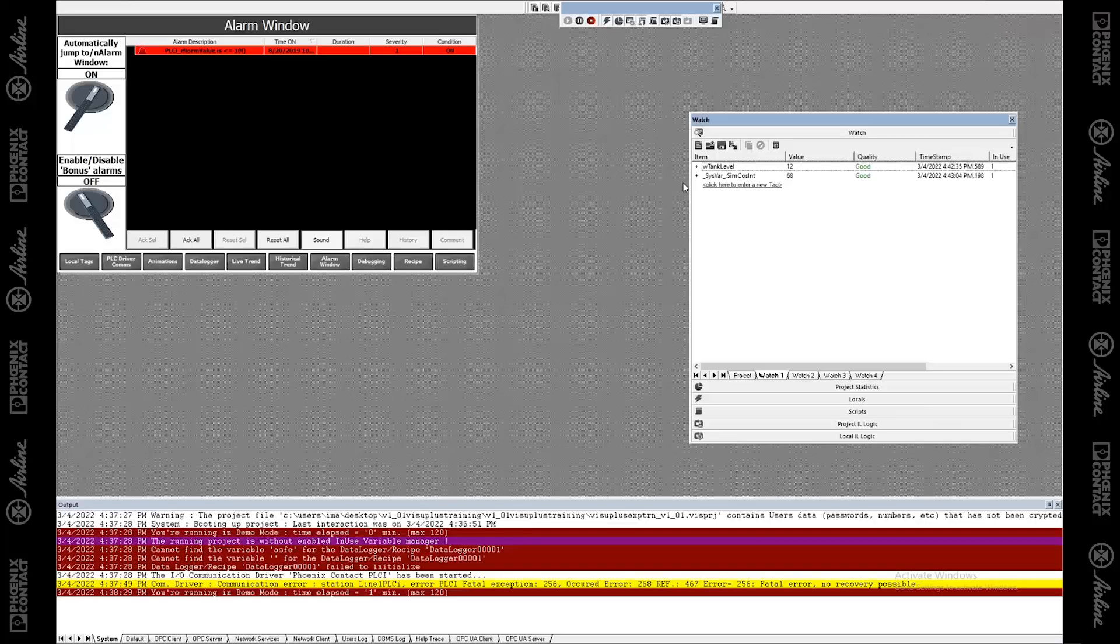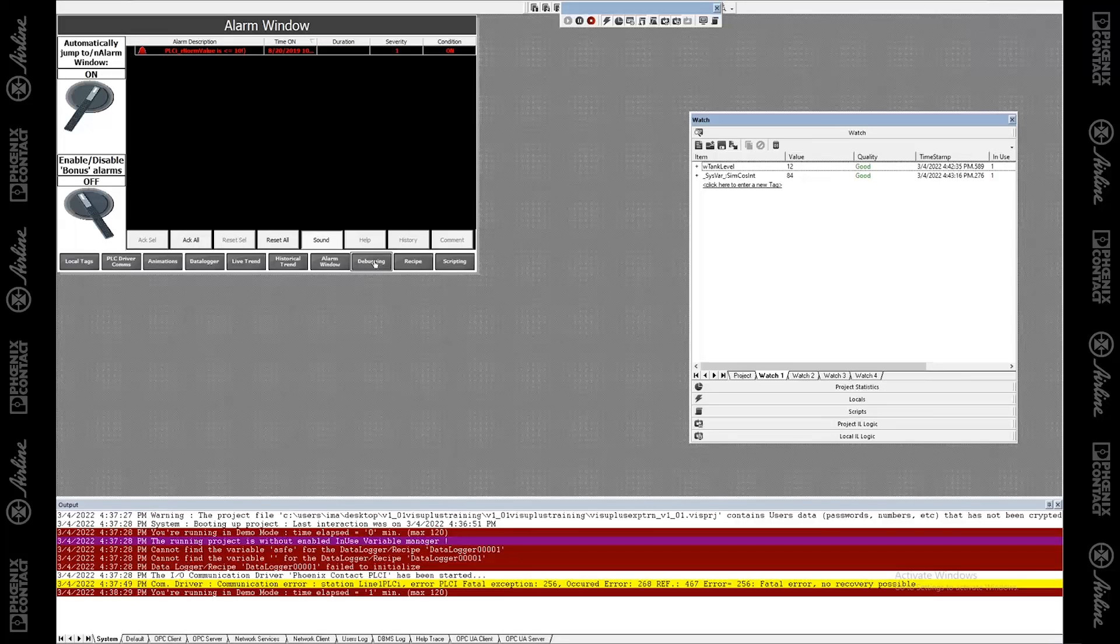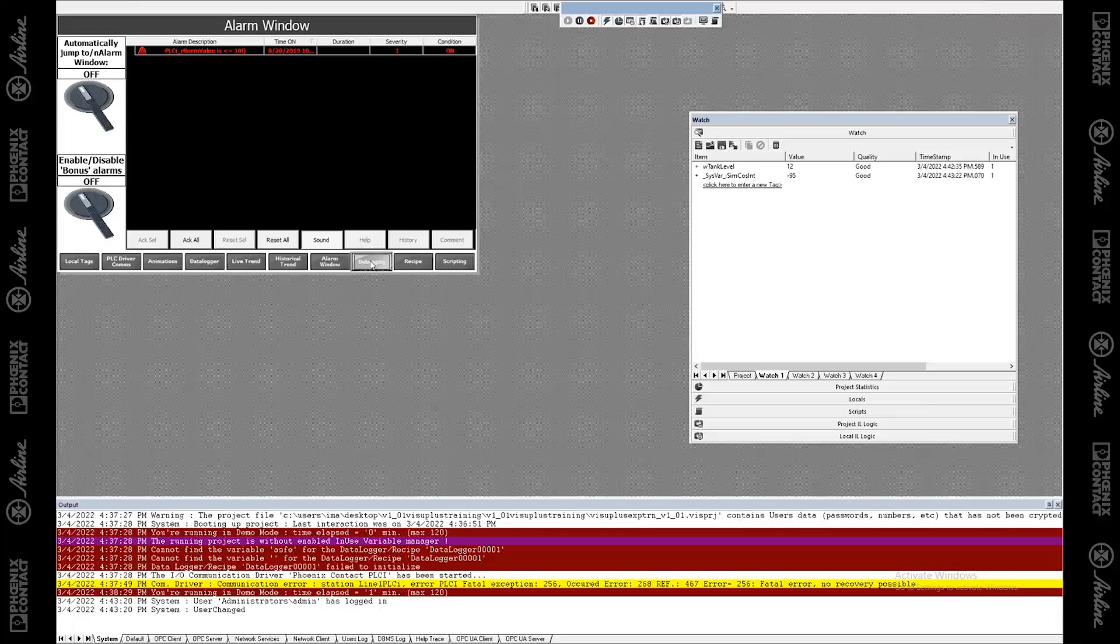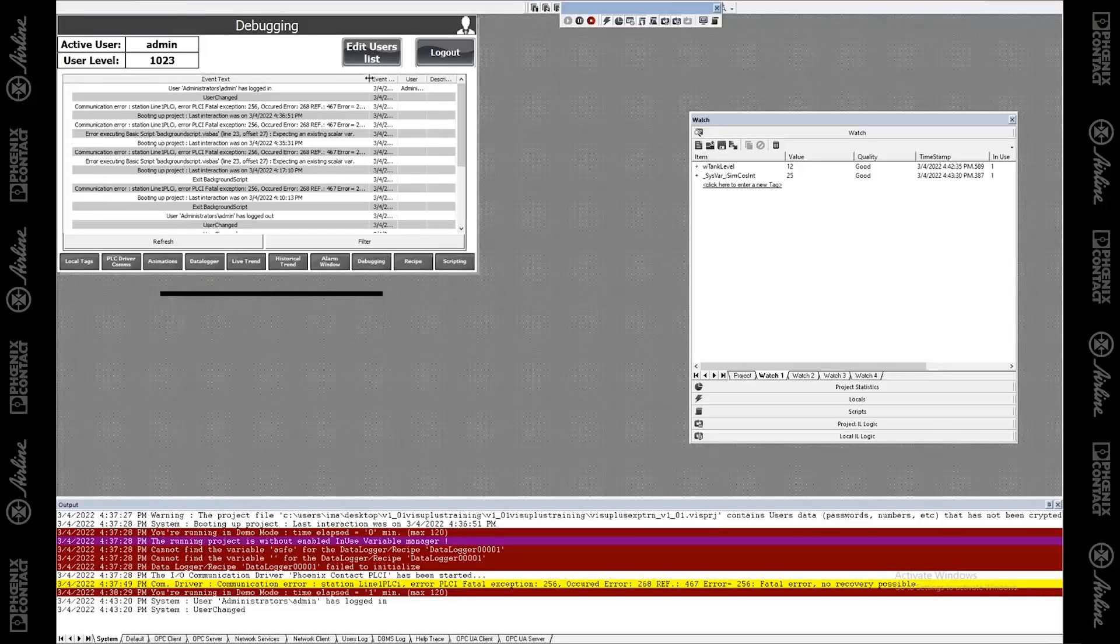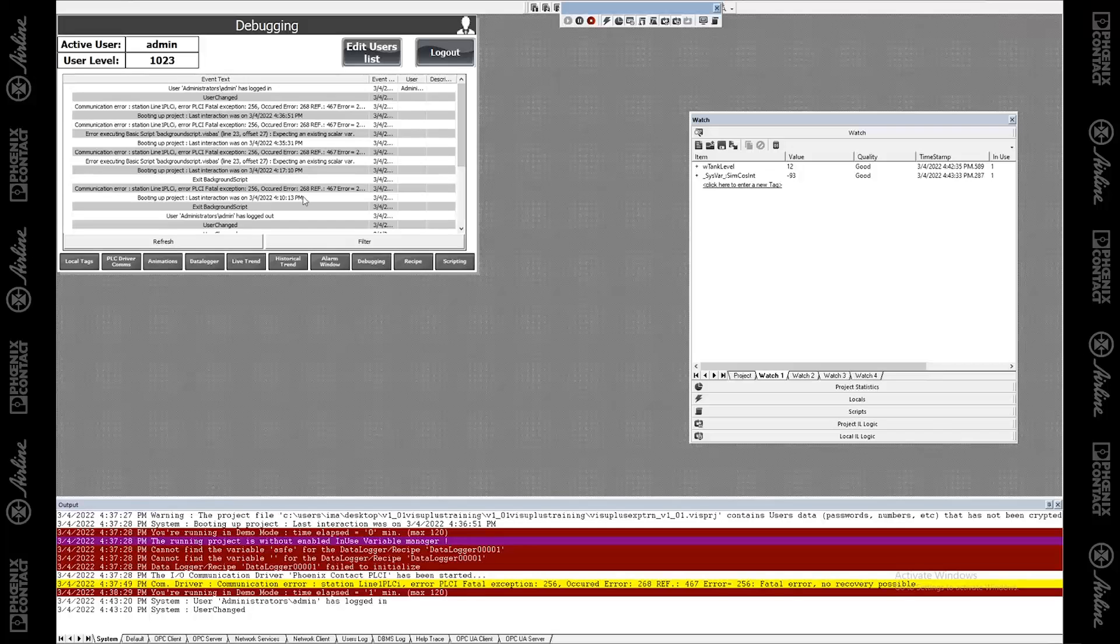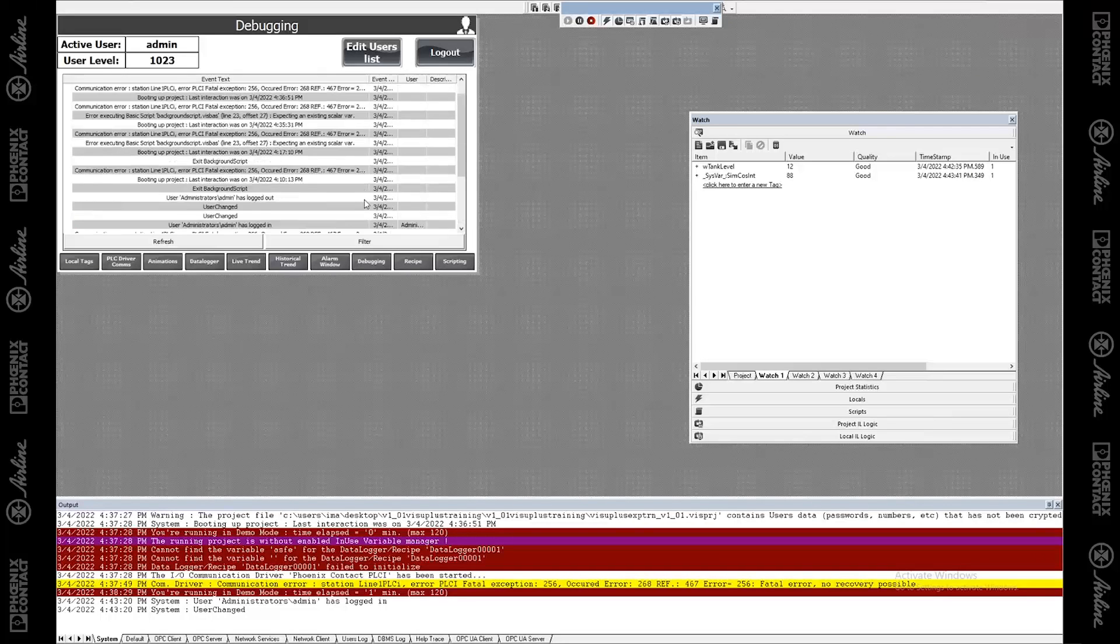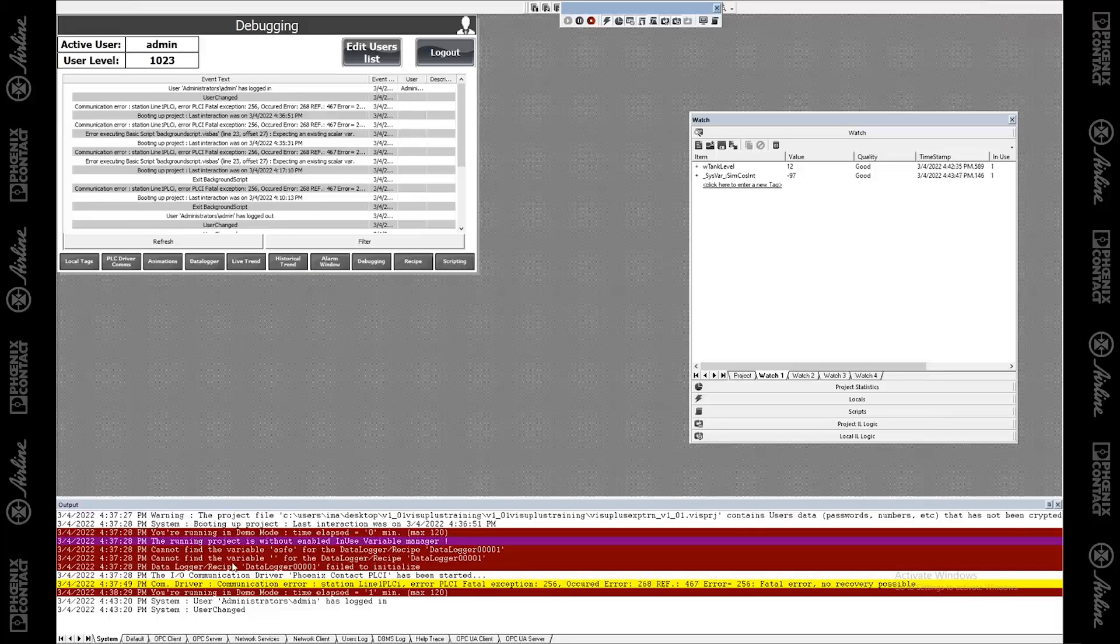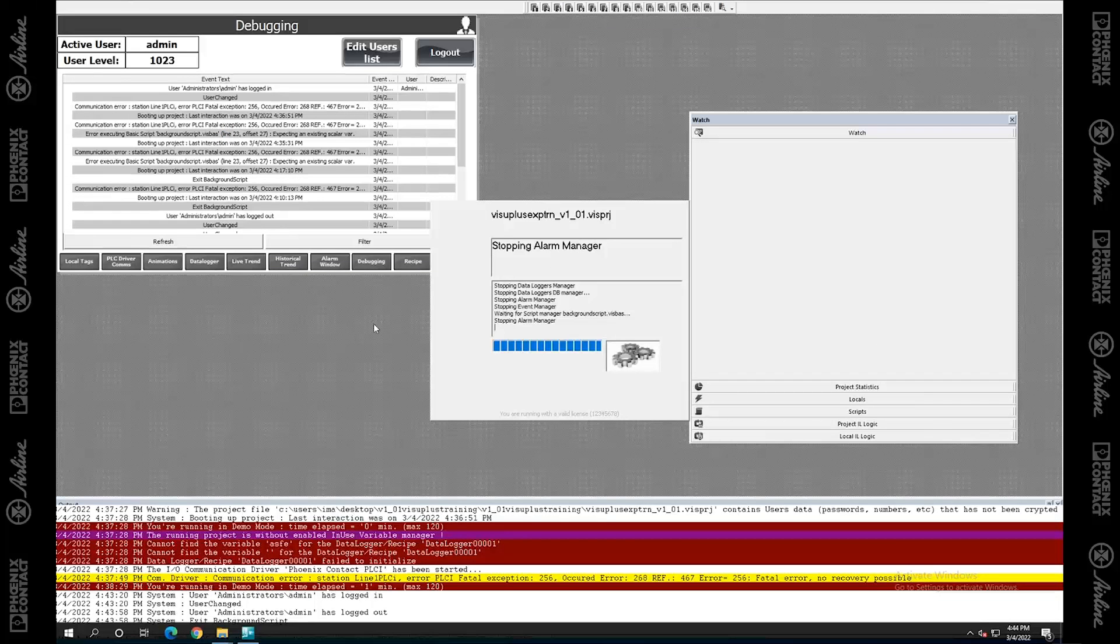Let's take a look at, I want to show you also a way that you can even see the logs that we were talking about before. You can actually display them in your screen itself. So I think I have that over here. That's debugging page. Yes, I do. So this is a log window. It's one of the objects in the toolbox. It's called the log window. And it allows you to see a list of your logs. It looks like this one might be showing all of my logs. So I can see there was an alarm that happened. And I can also see communication errors that happened. So this one is showing me basically everything that it can find. And so you'll see basically all of this, that things in the output window, you should see in here as well. And you'll also see alarms that are getting triggered and things along those lines.